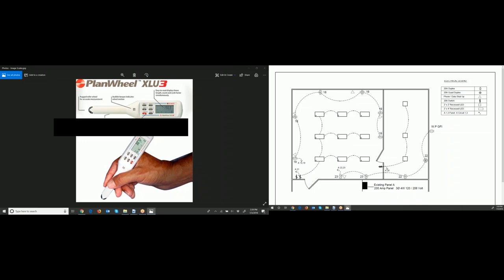I use the Scalex, set the scale, and roll this off. I usually over-roll to allow for the height. Say the distance is 12 feet and the ceiling height is 12 feet — the switches are about 4 feet — so I roll the Scalex across until I know it's about 10 feet, then roll over and up to the first light fixture and over-roll slightly to make up for the amount that goes down into the top of the fixture.